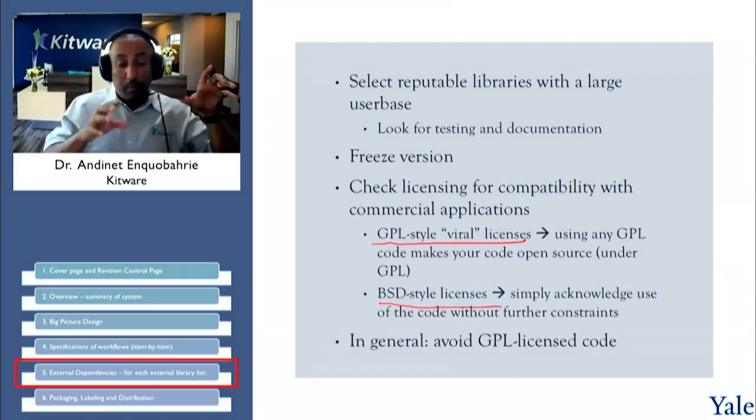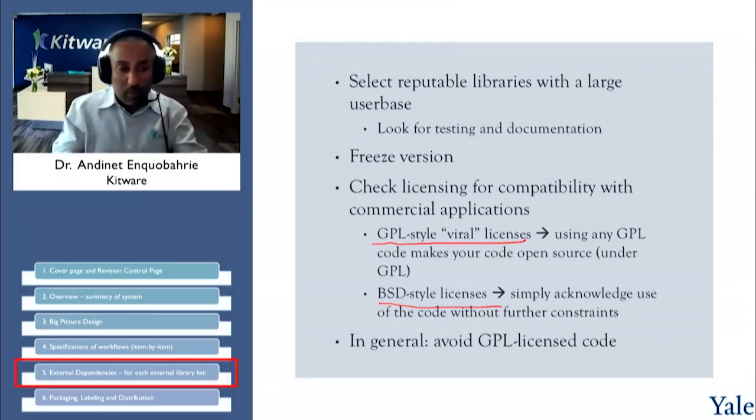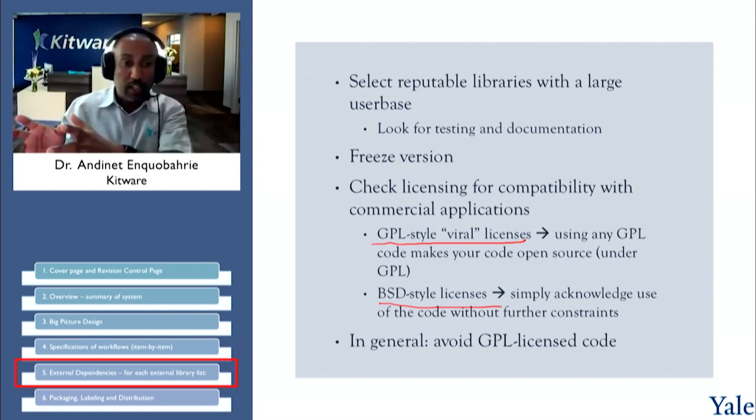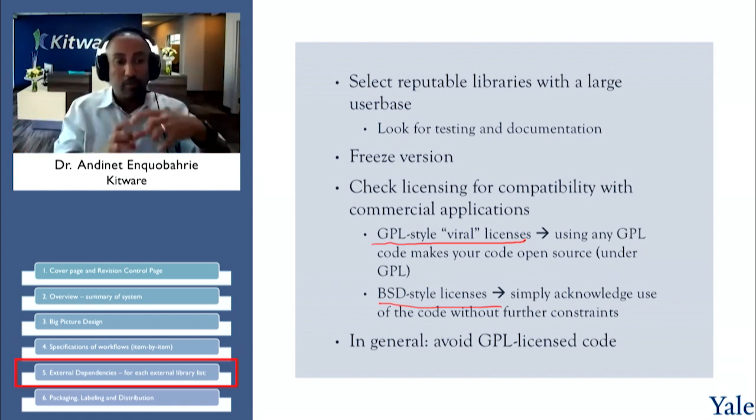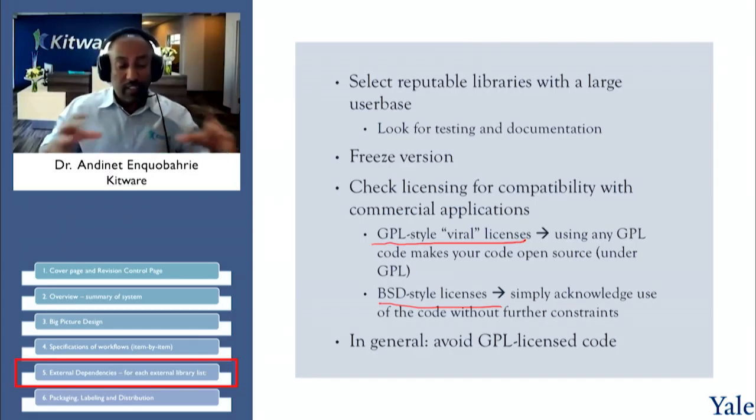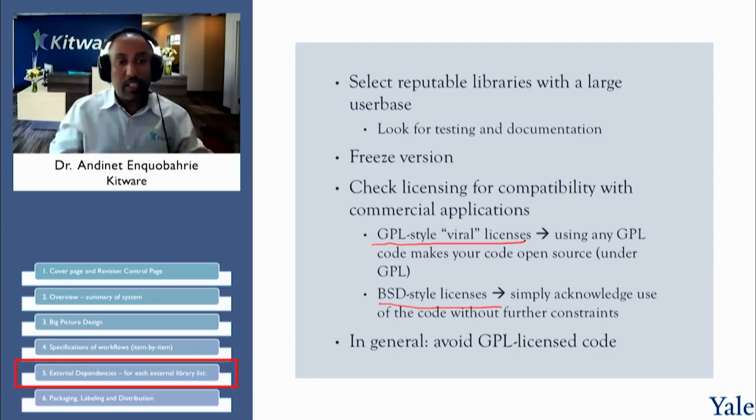But in fact, this is one of the requirements from FDA anyways, which is it's okay, you can use open source library, but they want you to lock down a particular version of VTK and ITK, and then put together a testing infrastructure around it, and then rigorously test that particular version, right, internally. And that's going to be part of your product development.